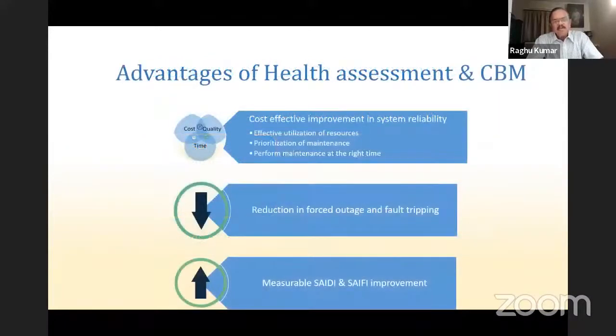The advantage of health assessment is a cost-effective improvement of system reliability. System reliability is dependent also on the design factors. As far as Qatar is concerned, 400 kV systems are N-2. That is, even if 2 assets fail, still the system will be stable. Below 400 kV, it is all N-1. One asset fails, the system can survive. So that design factor is also very important.